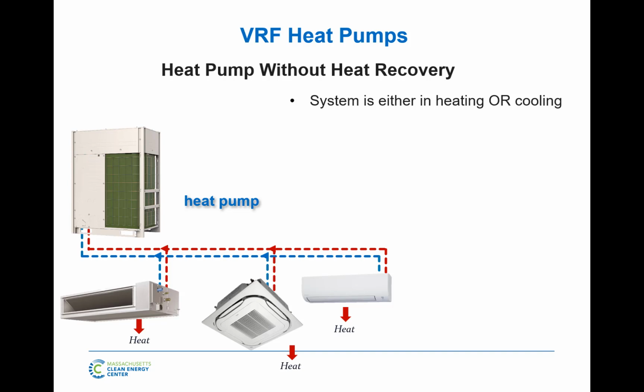And if I go into cooling mode, the opposite happens. This condenser is just delivering you liquid refrigerant. So you can take it and expand it and cool the space, and you can tell me how much of it you want, but that's all you can do. You can be off, but you can't be heating. There's no heating available. So kind of like a two-pipe chiller fan coil system. Either the chiller's on and you're in cooling in the summer, or you've turned your chiller off and it's winter period and your boilers are on and you're only in heating mode.